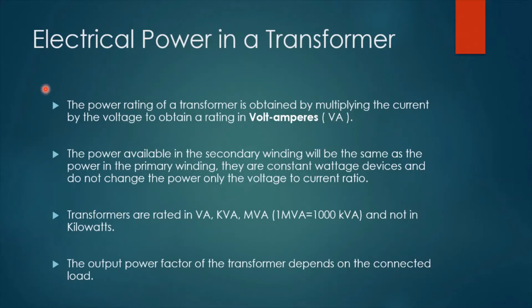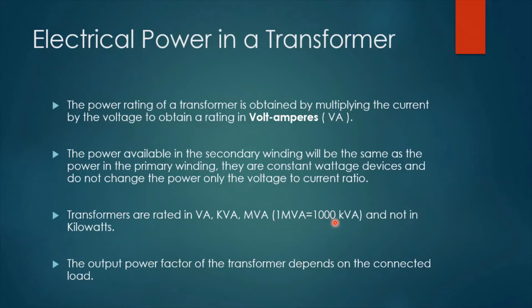Regarding electrical power in a transformer: the power rating of a transformer is obtained by multiplying the current by the voltage to obtain a rating in volt amperes (VA). The power available in the secondary winding will be the same as the power in the primary winding. They are constant wattage devices and they don't change the power, only the voltage to current ratio. The power will remain constant but the voltage will change from the primary to secondary transformation. Transformers are rated in volt amperes, kilovolt amperes, or megavolt amperes — noting that one megavolt ampere equals 1,000 kilovolt amperes — and they are not rated in kilowatts.